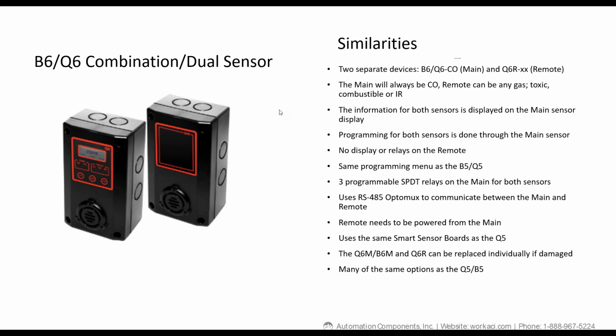What we did was we took the LCD off of the second box and made everything visual. For example, on carbon monoxide, usually mounted at 5-6 feet in the air, and say an NO2 sensor is mounted down around 18 inches—well, you don't want to get down on your knees to look at the screen, so everything's visible for CO and NO2 up at the CO level. It's a scrolling screen that just keeps going, and it shows you the parameters for both gases.